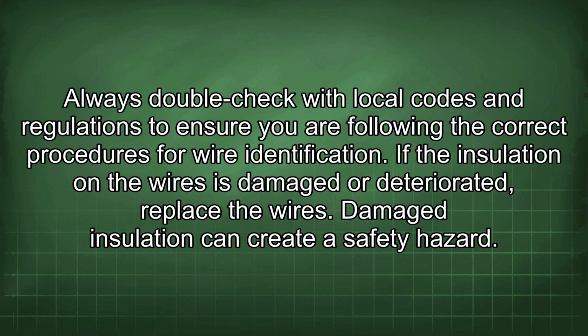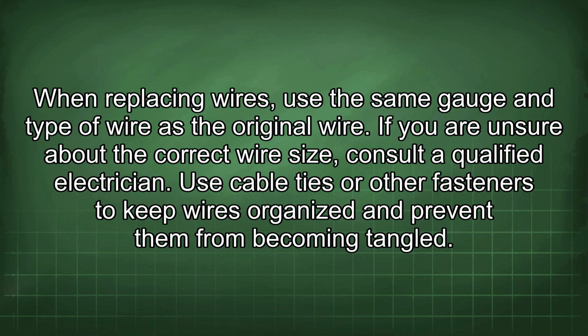If the insulation on the wires is damaged or deteriorated, replace the wires. Damaged insulation can create a safety hazard. When replacing wires, use the same gauge and type of wire as the original wire. If you are unsure about the correct wire size, consult a qualified electrician.